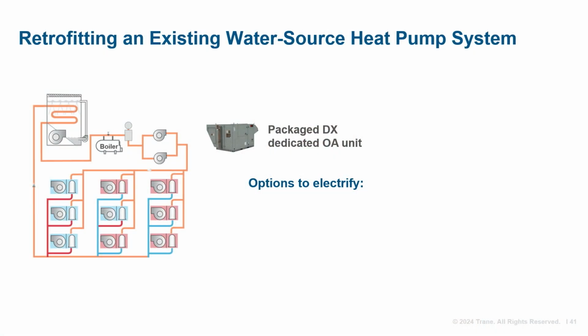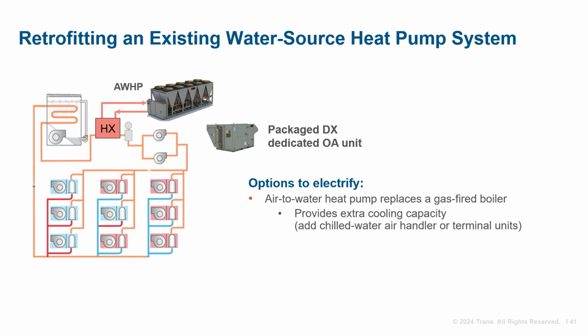Let's look at another common existing system, that being a water source heat pump system. What options are available to electrify this system in an existing building? One option is to replace the gas boiler with a heat pump to inject heat into the loop during cold weather. This offers the added benefit of providing some extra cooling capacity during warm weather.